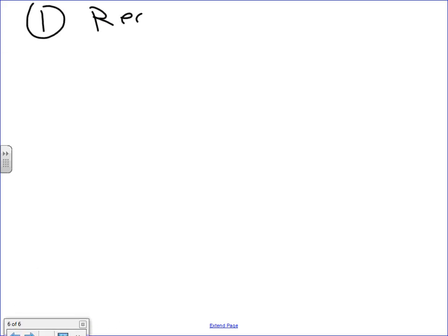So I'm going to start with type number one. I'm going to call it type number one, guys. Number one is receptacle circuits. And everybody knows that we are separating the receptacle circuits from the lighting circuits, from the equipment circuits, right? We don't take a circuit from here to feed this lighting fixture, Ashley, and this receptacle down there, and a fan in the end. You can if you size it right. Bad design, bad idea. Cheap, I can do it, can make it work based on the amps. Not a good idea. Not a good design. Okay, so receptacle circuits only feed receptacles.